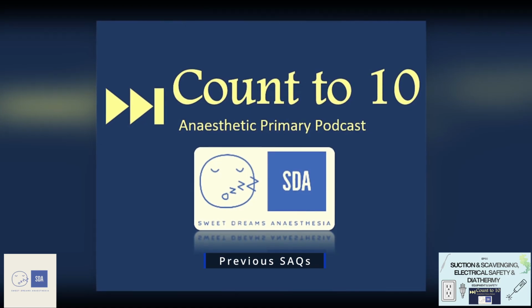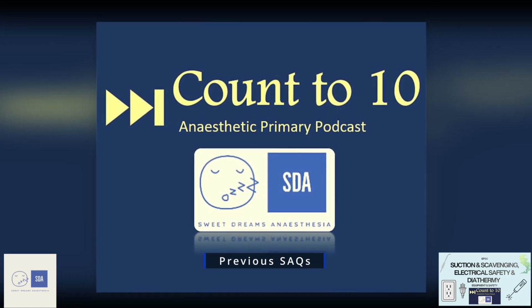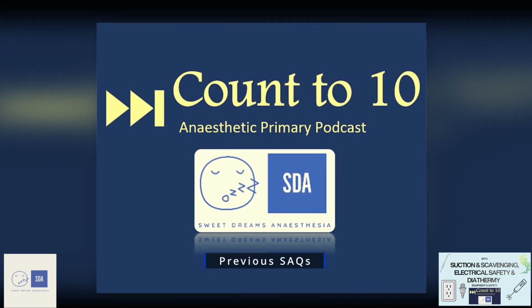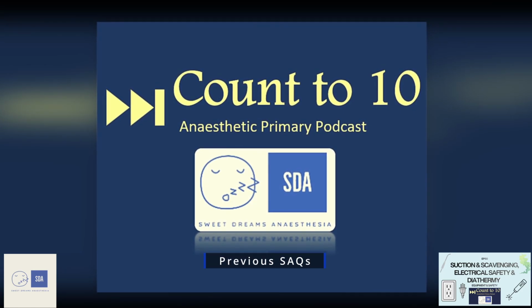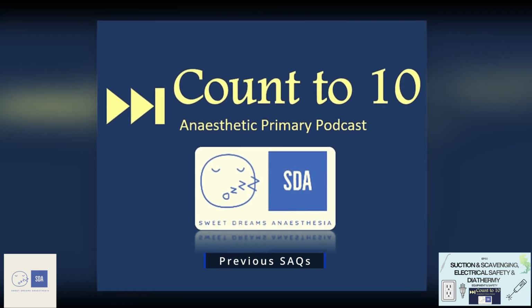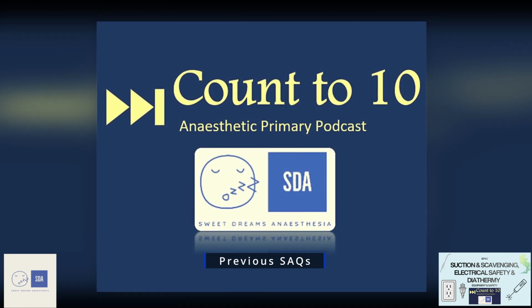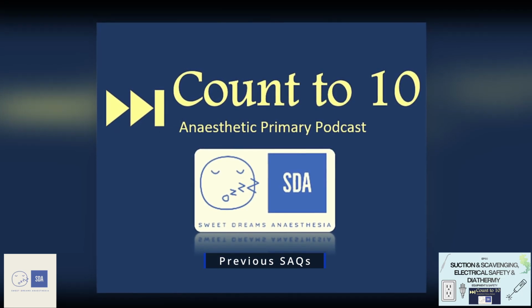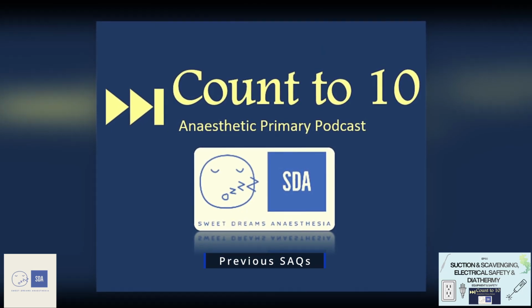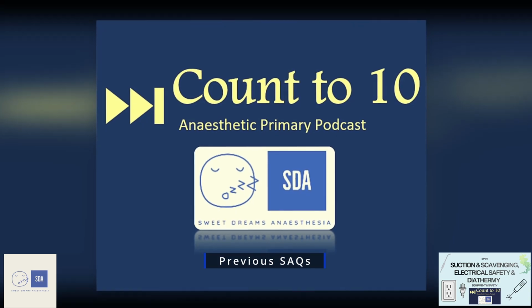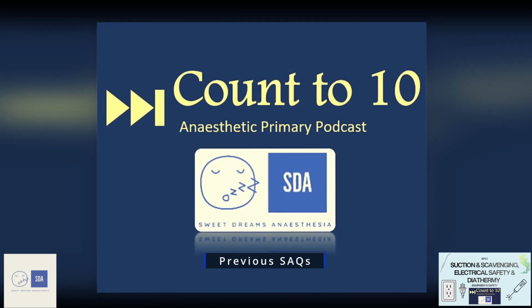The main mechanism of action, or the principle behind it, is the principle of current density, which is that the amount of heat that's generated when a current passes through the body depends on current density, and current density is equal to the current divided by the area. In terms of types and surgical effects, you can change the order of these, and I would go with dividing the types first, being monopolar and bipolar, which we've already spoken about, and then the effects of diathermy being either cutting, coagulation, and blended. And this is all related to the waveforms of that diathermy, with the cutting being lower voltage and a continuous high frequency sine wave, coagulation being a higher voltage and a higher frequency, which is given in a short burst, and then blended, which is a mixture of the continuous and the damped sine waves.